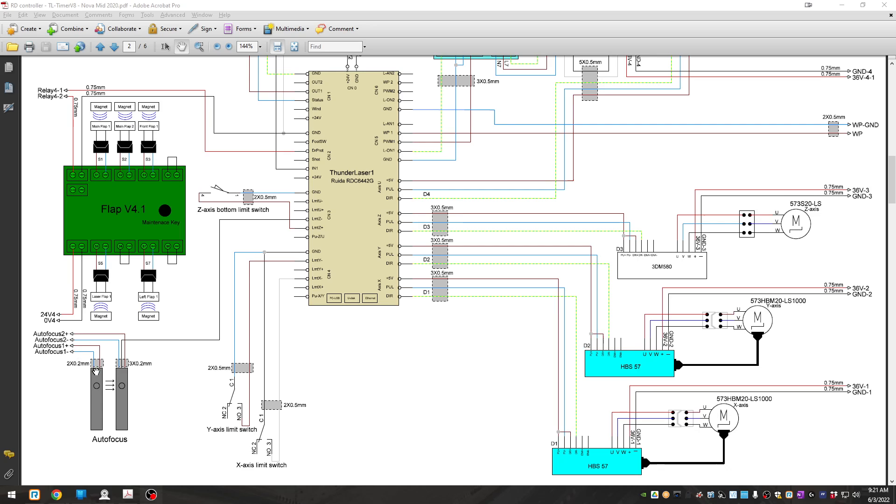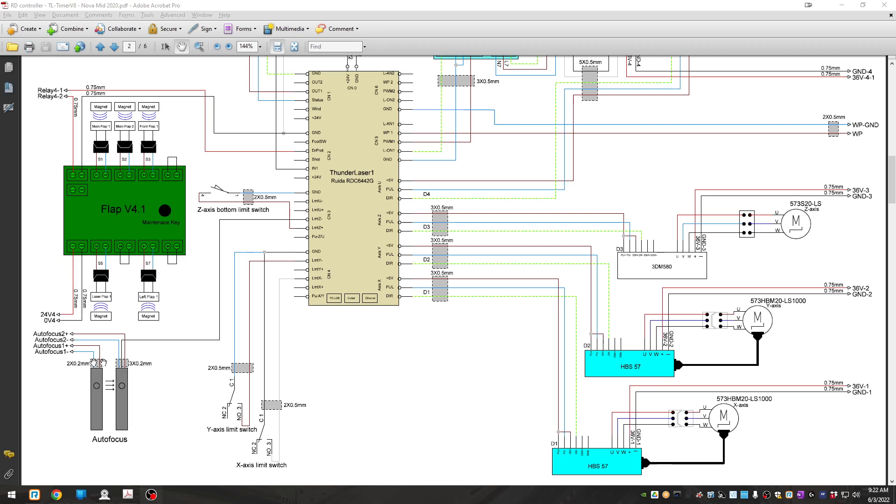we should be able to take the autofocus sensors loose at their connectors and measure across the two pins on the transmitter and get 24 volt DC. And across the proper two connections on the three pin connector and also get 24 volt DC. And then we can plug those back into the circuit and go further.